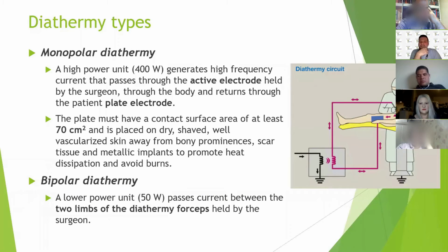Now, there are two types of diathermy, the monopolar and the bipolar. We all know them. It's how you describe them in the exam. So the monopolar, you enter the electricity into the body on one side, it passes through the body, and gets out of the body over a receiver that is attached to a part of the body, and then it goes to the machine. Previously, it used to be earthed, but now they go to a special machine to protect patients from differences in or problems with electricity. The plate has to be 70 centimeters square, and it has to have full attachment to the body with no hair or wet surfaces. Okay.